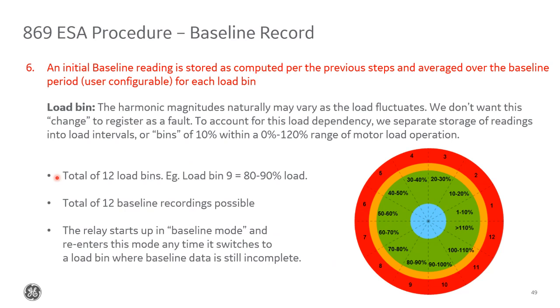In step six, in the relay settings, there's an option for a baseline period. For however long this period is set, while the motor is in service and running, we continually take a recording of the peak magnitude values that we calculate repeatedly per the last step.